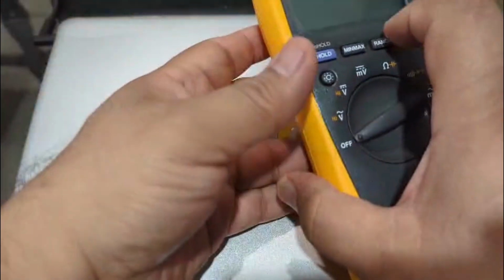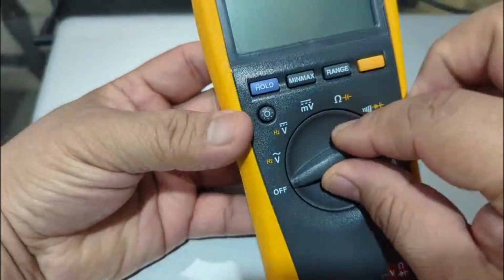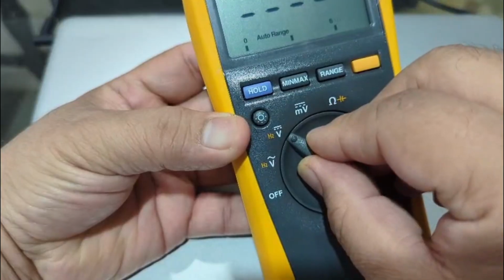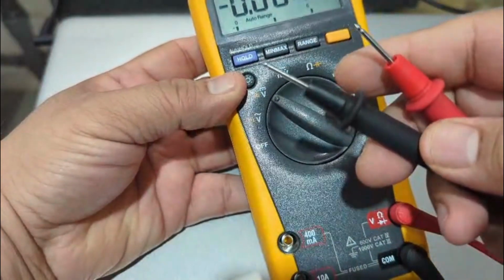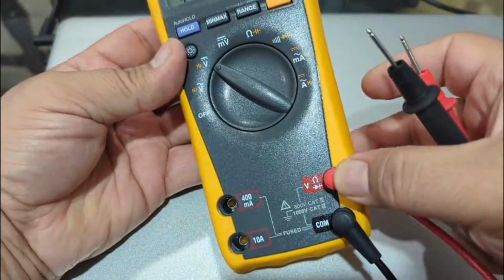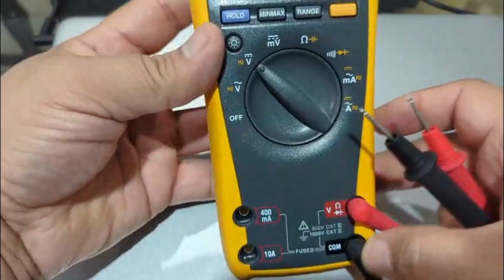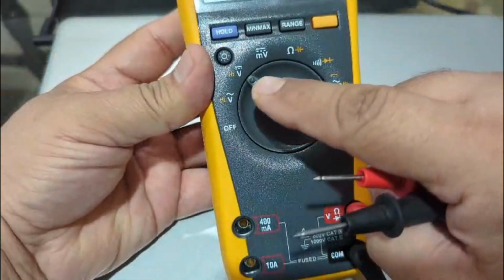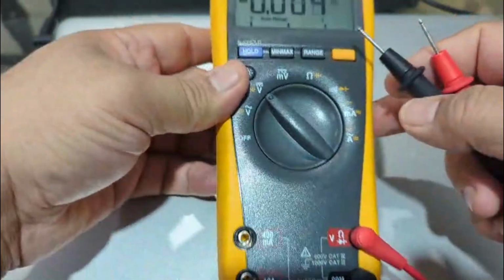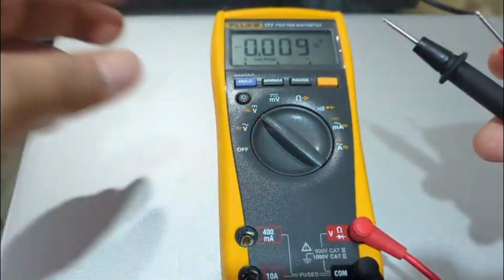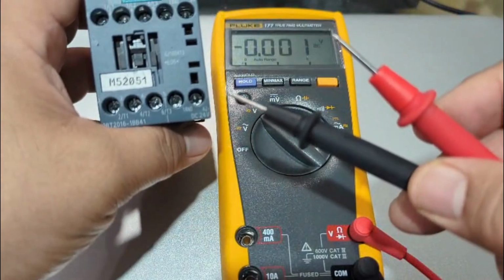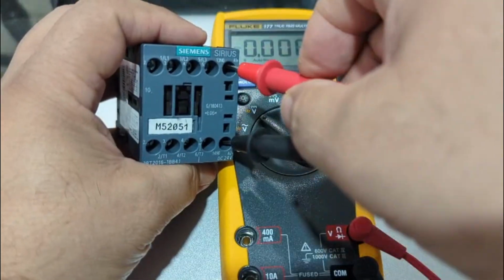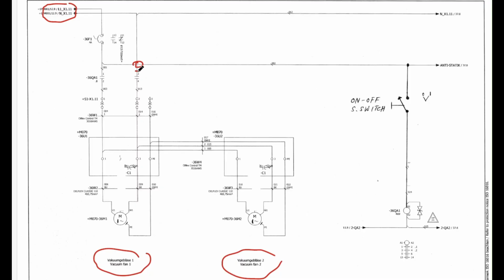And here I show you, if you want to check supply, we select DC, and these are the probes. One is connected at positive, you see the V voltage, and black is common. So when we want to check 24 volt DC, we select the voltage and DC, and then you can see here it shows negative. Then we connect negative here, positive here, and we check the voltage anywhere, because black is common. And the red probe will check at this terminal.